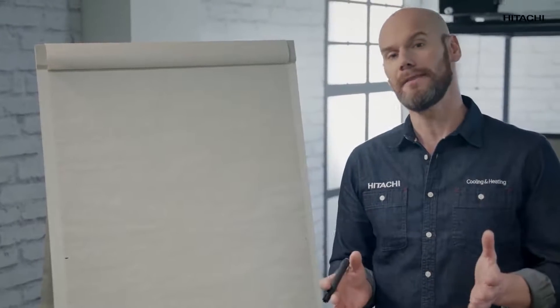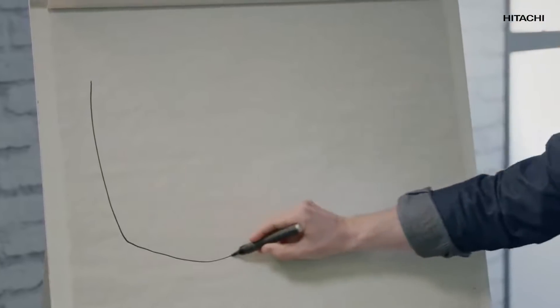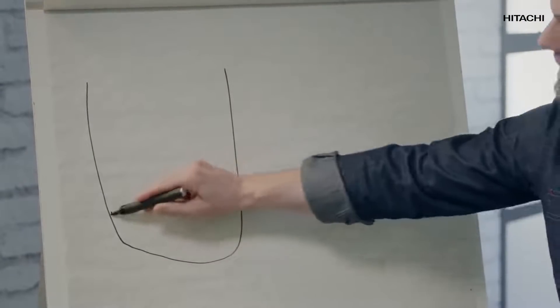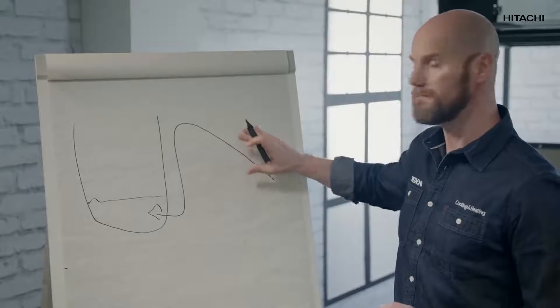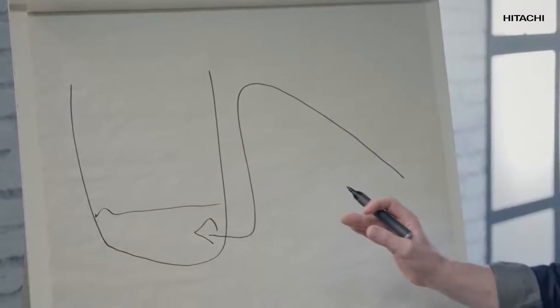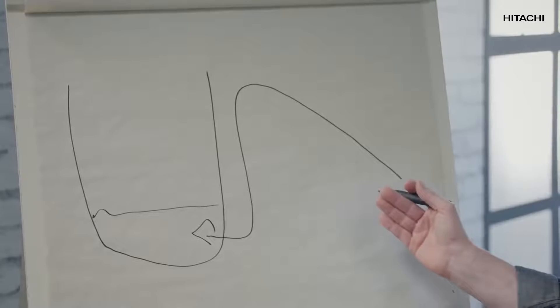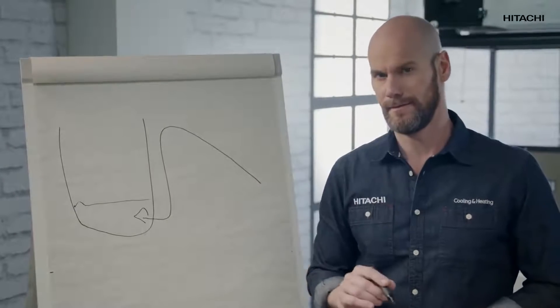We've already verified that a fault is not in the pump. This illustration will help us rule out a fault in the drain. As you can see, the drain must have a minimum descending slope. If that is not the case, the water probably won't come out and will return back to the pan. Then the alarm goes off.